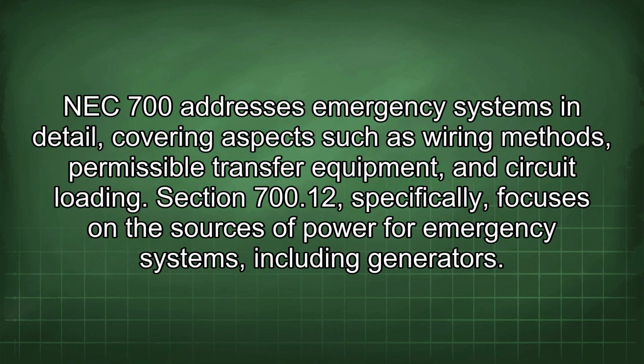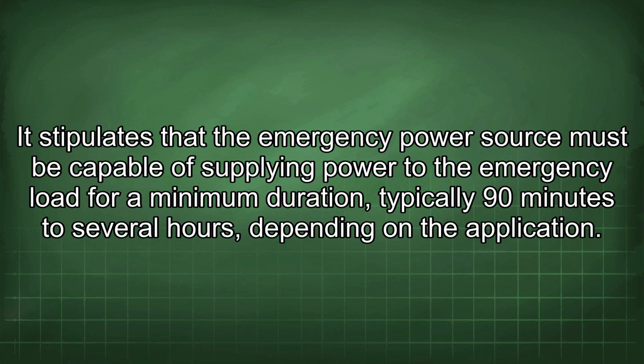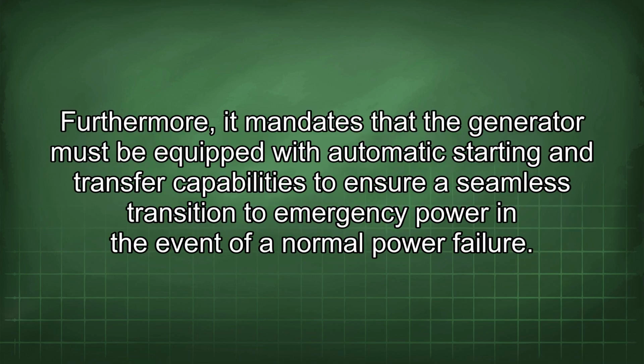NEC 700 addresses the emergency systems in detail, covering aspects such as wiring methods, permissible transfer equipment, and circuit loading. Section 700.12 specifically focuses on the sources of power for emergency systems, including generators. It stipulates that the emergency power source must be capable of supplying power to the emergency load for a minimum duration, typically 90 minutes to several hours, depending on the application. Furthermore, it mandates that the generator must be equipped with automatic starting and transfer capabilities to ensure a seamless transition to emergency power in the event of a normal power failure.